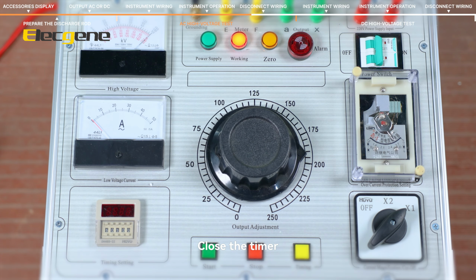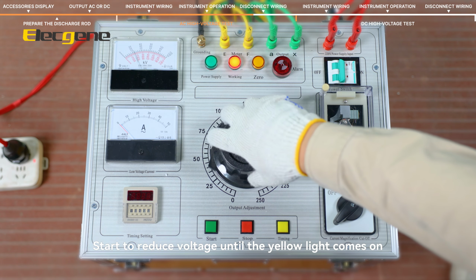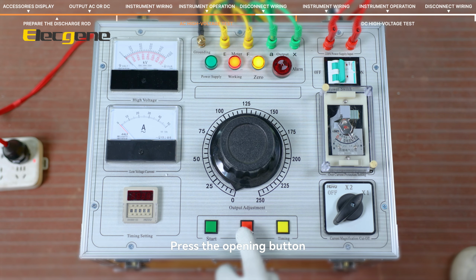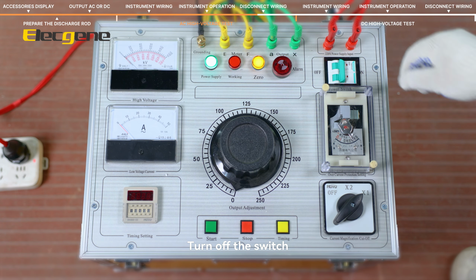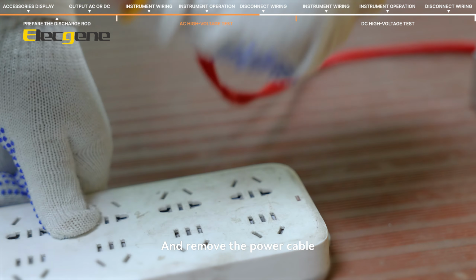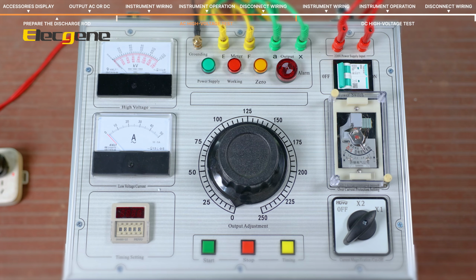Close the timer. Start to reduce voltage until the yellow light comes on. Press the opening button, turn off the switch, and remove the power cable. Disconnect wiring.